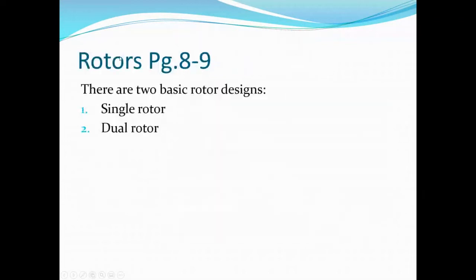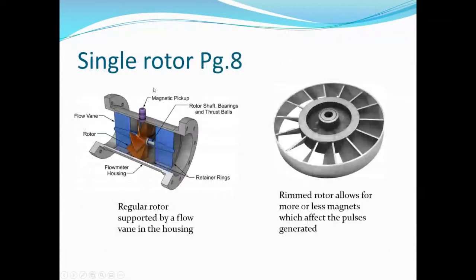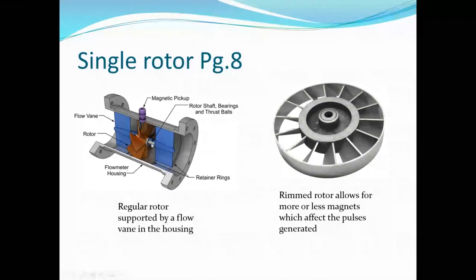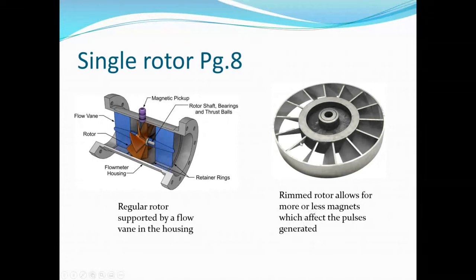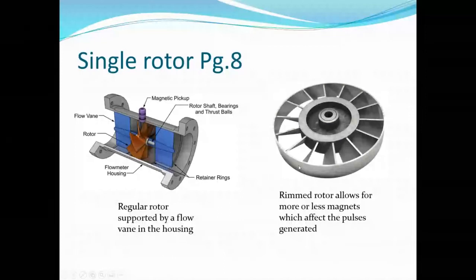Looking at rotors in more detail, there are two basic rotor designs: the single rotor and the dual rotor. The single rotor is supported by stators in the body with bearings. Sometimes the rotor is rimmed — this relates to allowing more or less magnets, which increases or decreases the number of pulses generated. There's a magnetic interaction with a coil generating these pulses, and the rimmed rotor allows adding or removing magnets.